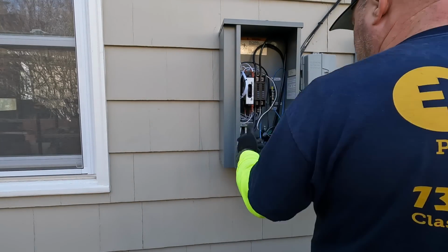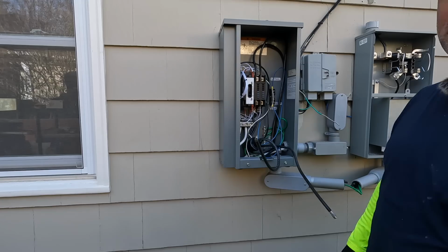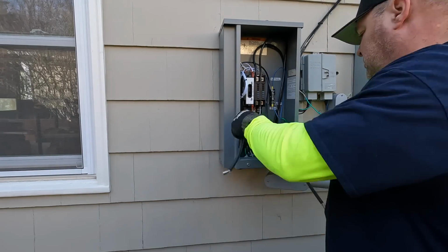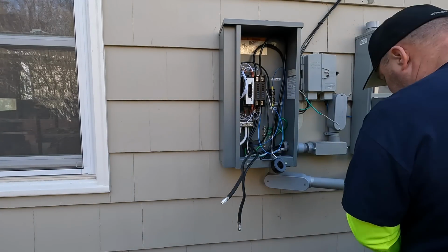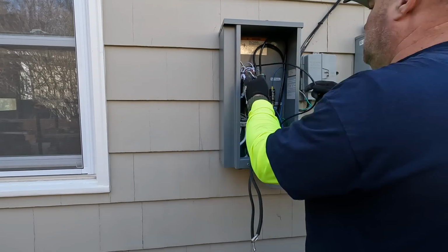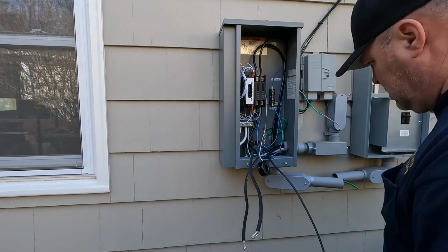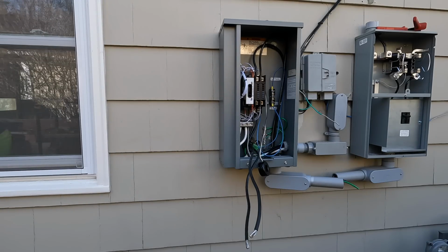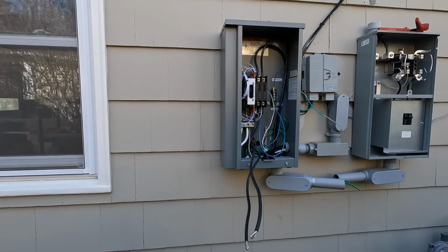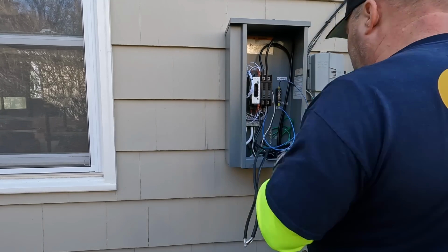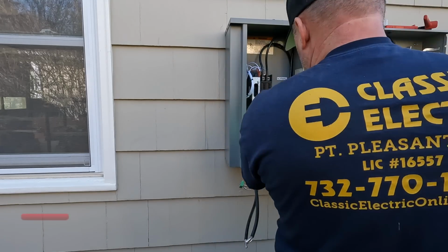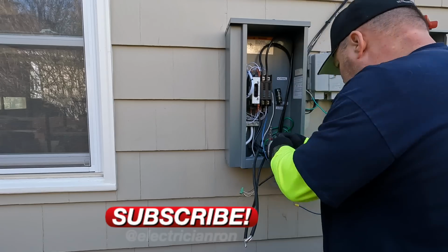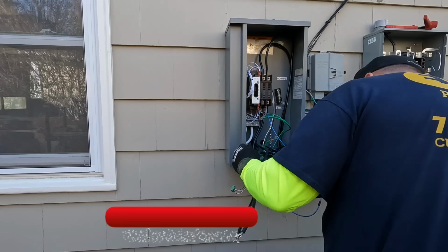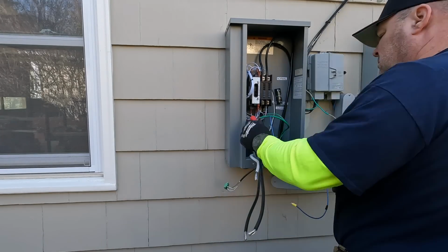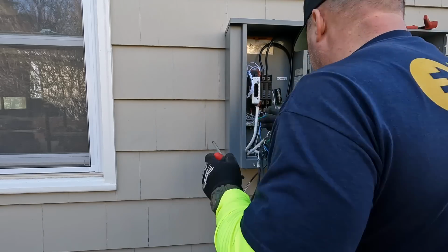So when you have a non-rated service disconnect for the transfer switch, or the automatic transfer switch that's service rated, when I take this out, what I need to do is put in a whole house transfer switch that's service rated. That means I won't need to put in that emergency disconnect you see now in that 100 amp panel, because the automatic transfer switch will be service rated, so that will be the emergency disconnect and the automatic transfer switch as well. Of course, when you do that and use it as the main disconnect, it has to be service rated. That's in the code, and I'll put that code section up on the screen momentarily.